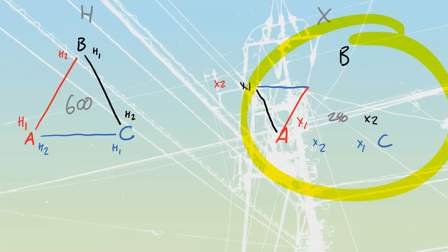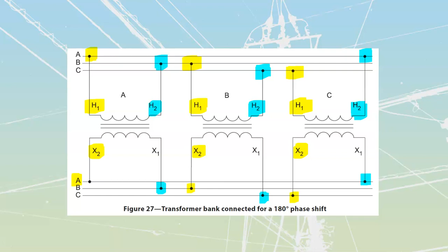In real life, we know that A line should be connected to my X1. But in this case, we see that my A line is connected to my X2. And that my B line's X2 is connected there, and the C line's X2 is connected there, which means that the rest of the connection, although it forms a delta and will spin three-phase loads, is going to give us a massive problem if we try to parallel onto a bank. You could do this as a standalone system, but it's not the standard, and it can hurt somebody else if they put anything else on.